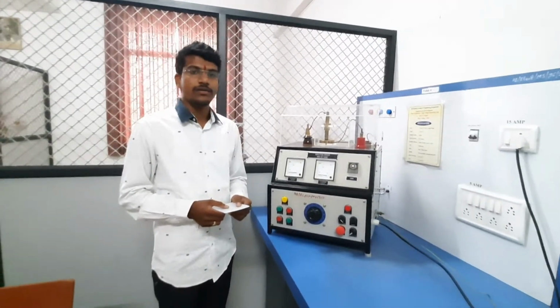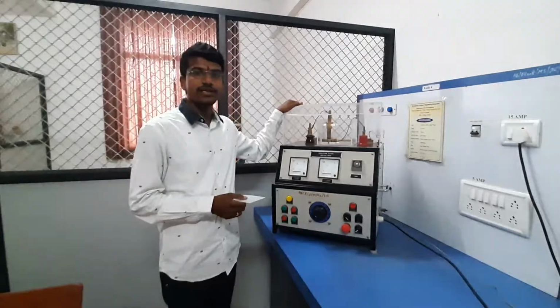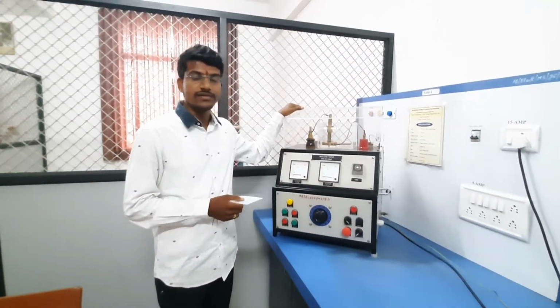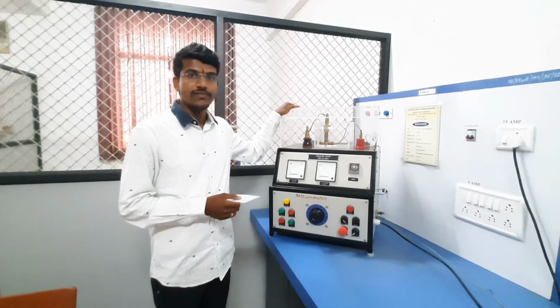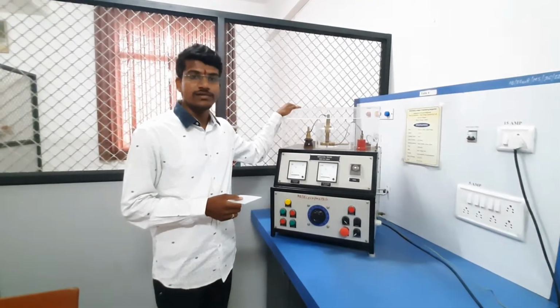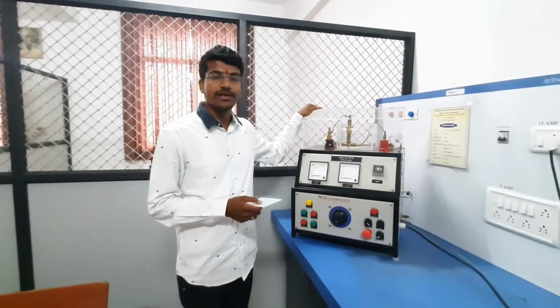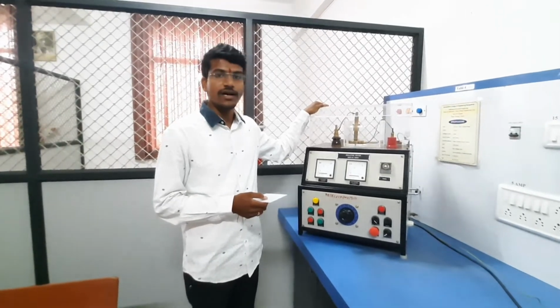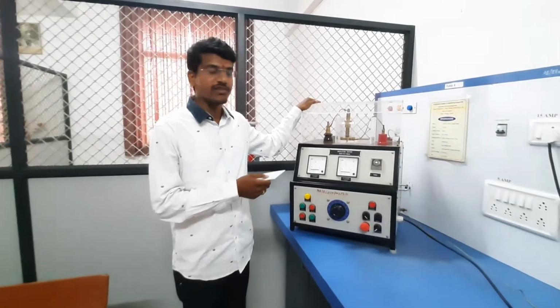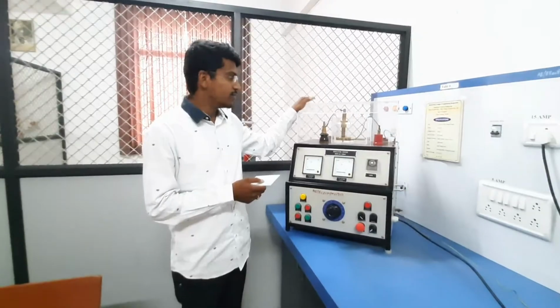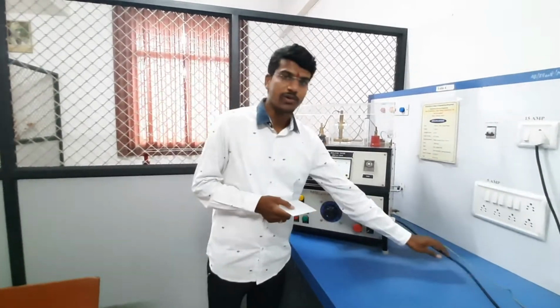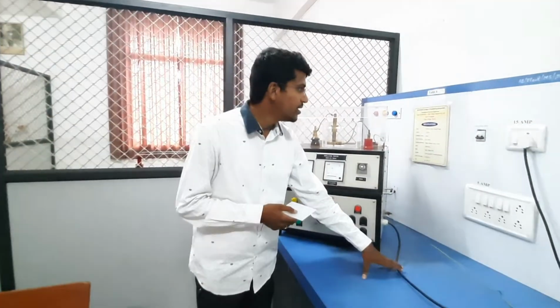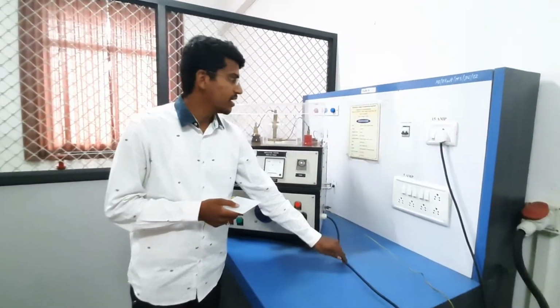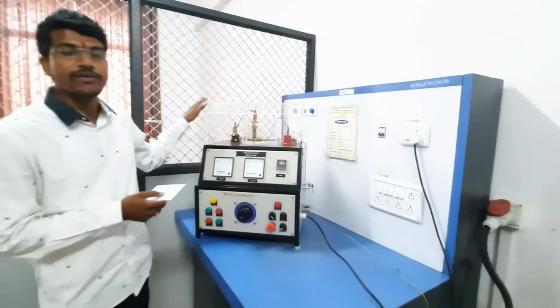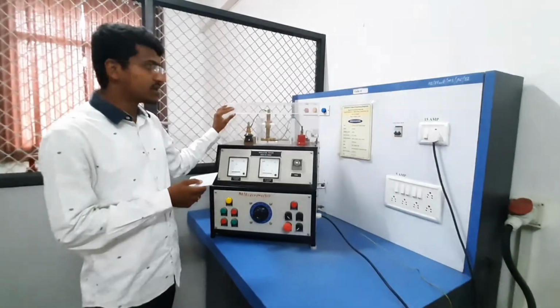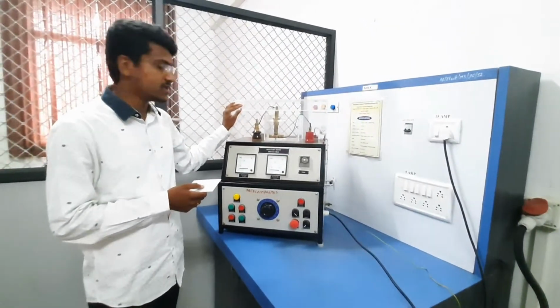This is a high voltage tester kit. In this kit, we perform the dielectric strength test of solid insulating material. This kit has the following specifications: input supply of 230 volt, 50 hertz AC, single phase supply, and secondary output of 0 to 30 kV voltage.